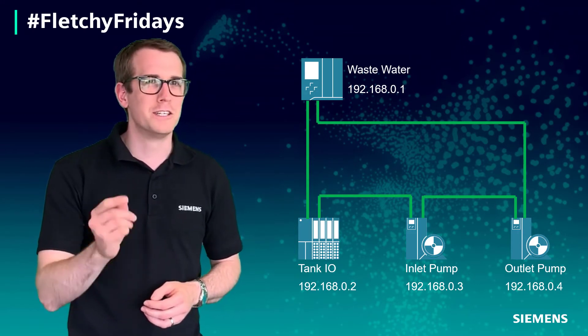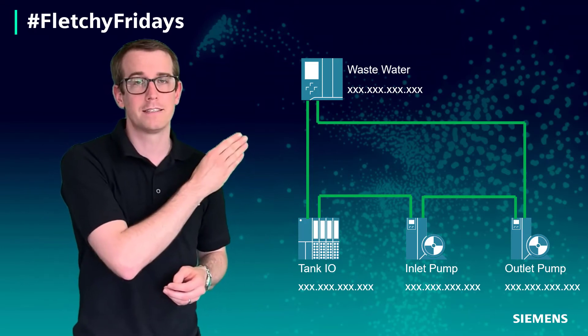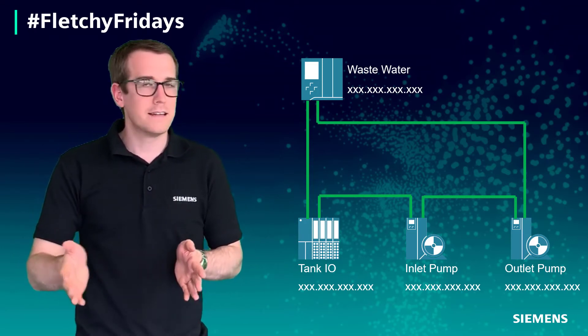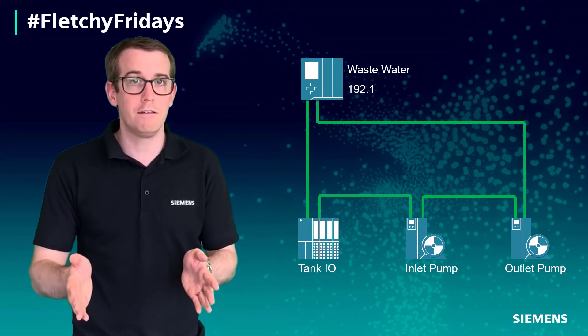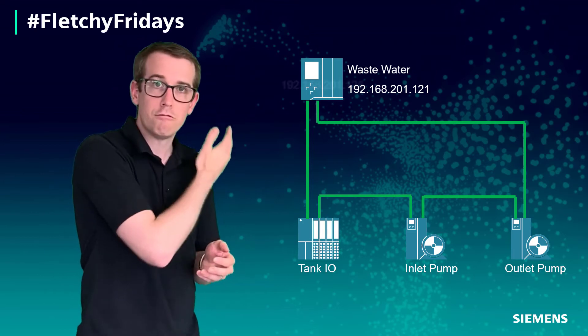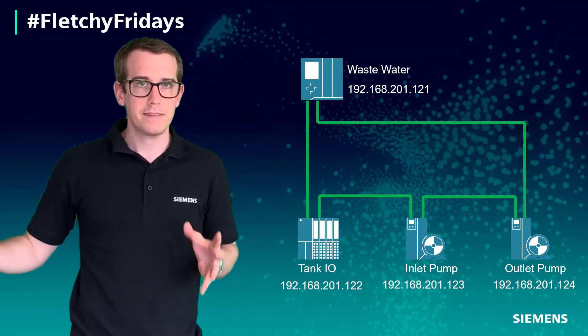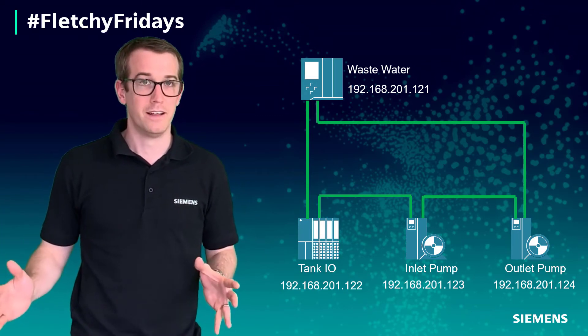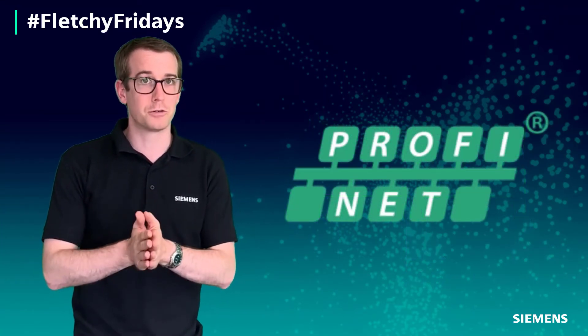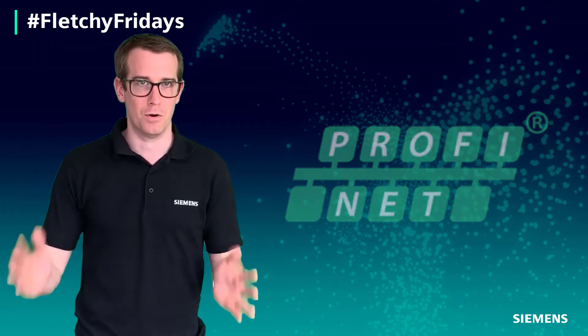What's really cool though is in the S7 1500 you can even assign the IP address at commissioning. So if you were integrated into a customer's site and they started to define what IP range they wanted you to use, you could do this at the controller and it will then ripple out the following IP addresses to all the devices it's managing. So loads of great reasons there why ProfiNet is a fantastic protocol to be using and over the coming months we'll be seeing even more.